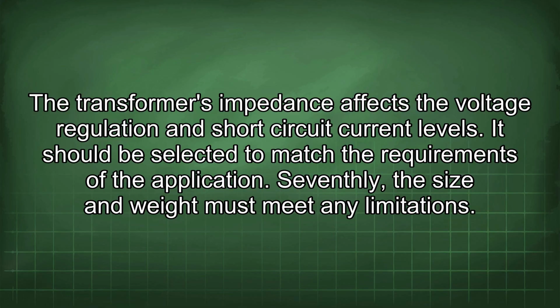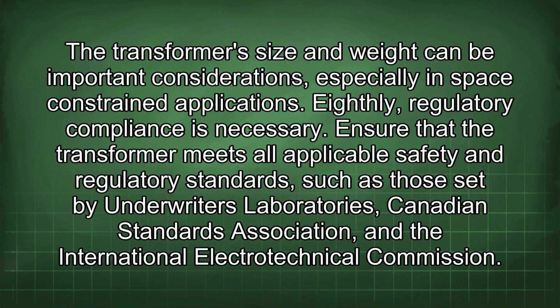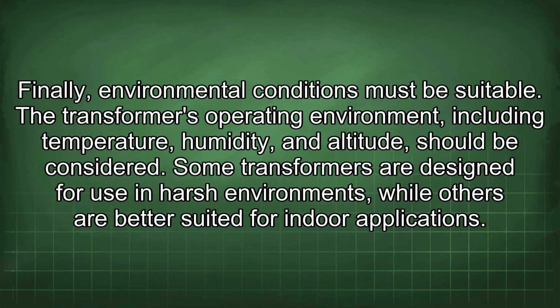Seventhly, the size and weight must meet any limitations. The transformer's size and weight can be important considerations, especially in space-constrained applications. Eighthly, regulatory compliance is necessary. Ensure that the transformer meets all applicable safety and regulatory standards, such as those set by Underwriters Laboratories, Canadian Standards Association, and the International Electrotechnical Commission. Finally, environmental conditions must be suitable. The transformer's operating environment, including temperature, humidity, and altitude, should be considered. Some transformers are designed for use in harsh environments, while others are better suited for indoor applications.